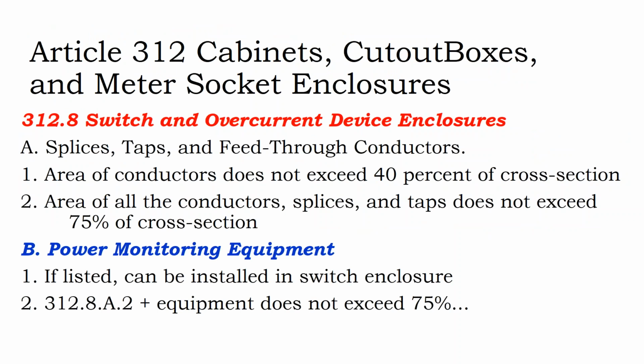We talk about how not just conduit, but boxes and junction boxes have minimal sizing. Generally you size to be no more than a 40% conduit fill. And you actually have less conduit fill for 2 wires than 3 or 4 just because of how they tangle up. But boxes are the same way. You design the boxes so the conductors inside them, just like conduit, can't be at that 40% fill. But you also have other stuff occurring inside a box, and that other stuff cannot exceed more than 75% of the junction box cross section.